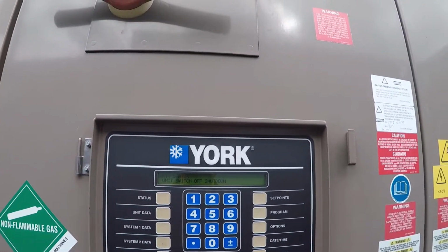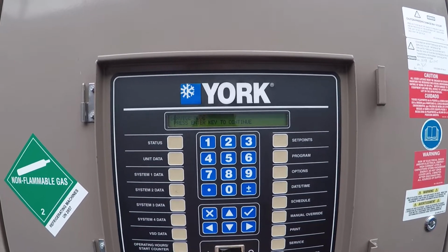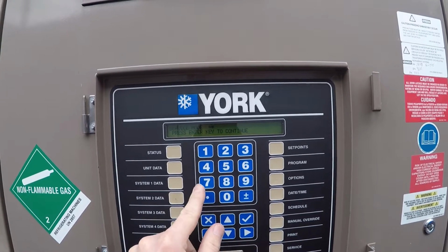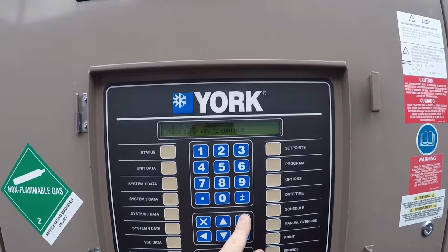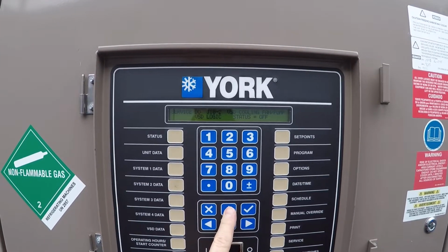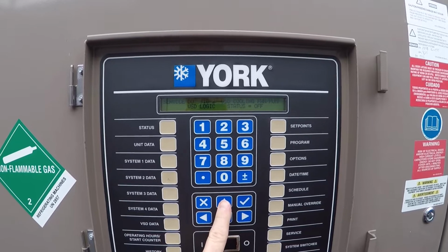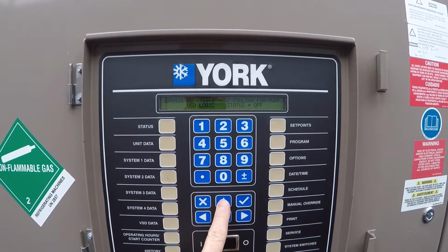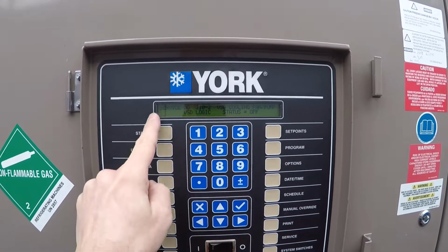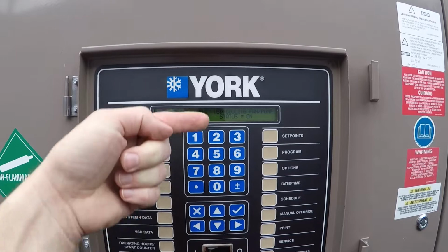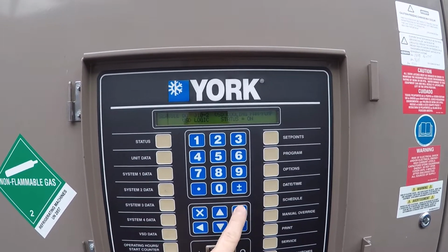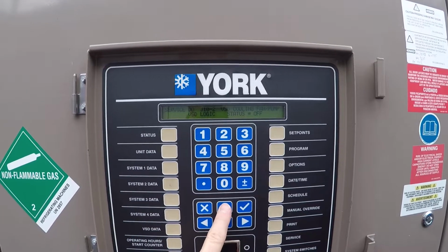So what happens is, if you get the service button and you put in a code of 9675, enter, that'll bring you into service mode where you can actually turn things on and off. Like if I want to test to make sure that my VSD cooling fan and pump works, I put in that little code, and then I go through the selection and just hit the tick mark, and I can turn it on and test it to make sure all the fans and the pump and everything is working. And then I can turn it off. And it doesn't stop there.